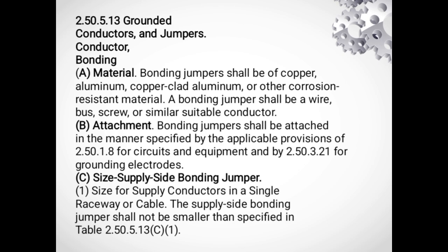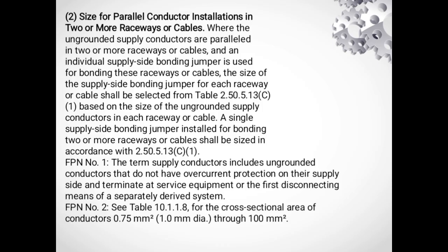2. Size for parallel conductor installations in two or more raceway or cables. Where the ungrounded supply conductors are paralleled in two or more raceway or cables, and an individual supply side bonding jumper is used for bonding these raceway or cables, the size of the supply side bonding jumper for each raceway or cable should be selected from Table 2.50.5.13 C1, based on the size of the ungrounded supply conductors in each raceway or cable. A single supply side bonding jumper installed for bonding two or more raceway or cables shall be sized in accordance with 2.50.5.13 C1. In number 1, the term supply conductor includes the ungrounded conductors that do not have overcurrent protection on their supply side and terminate at service equipment or the first disconnecting means of a separately derived system.